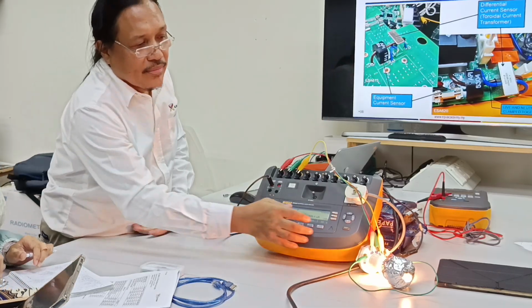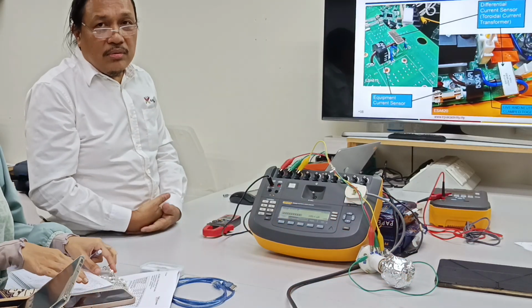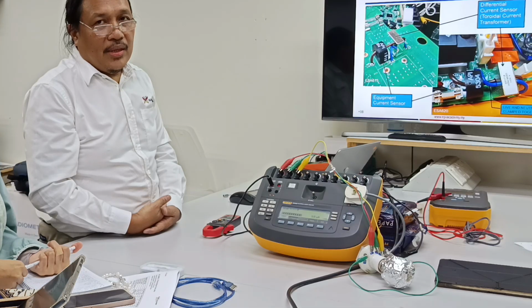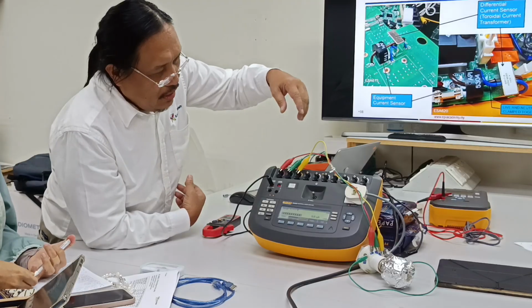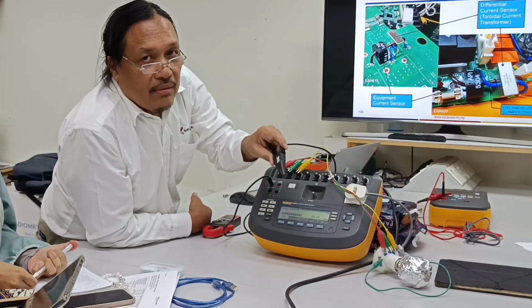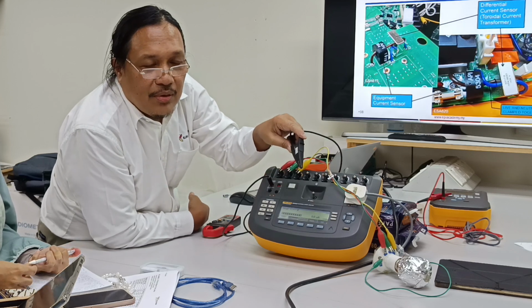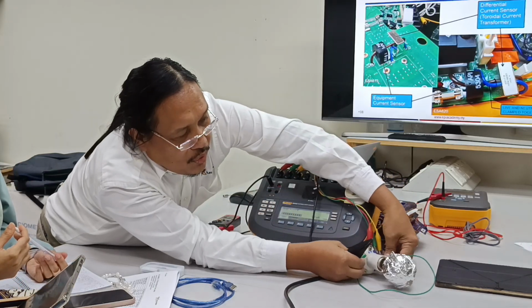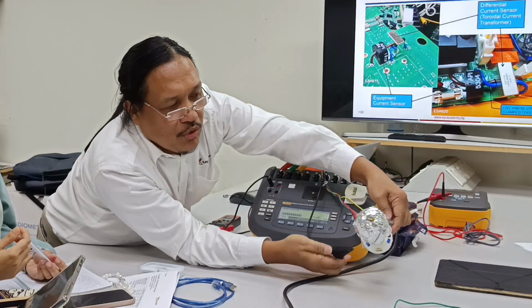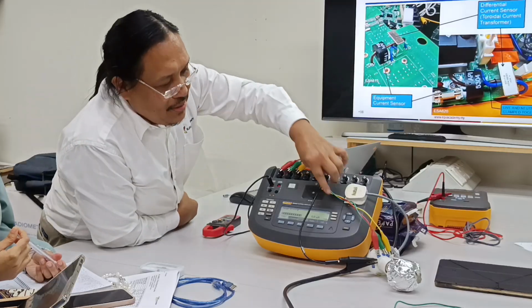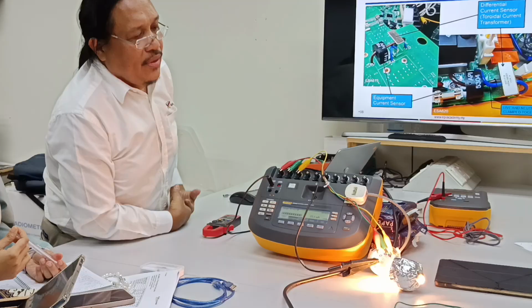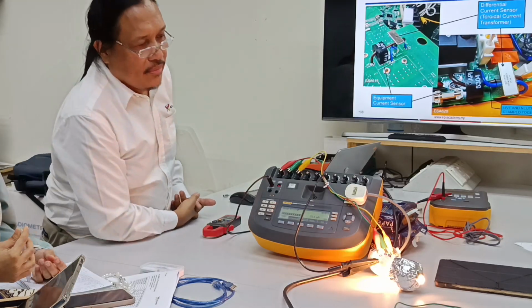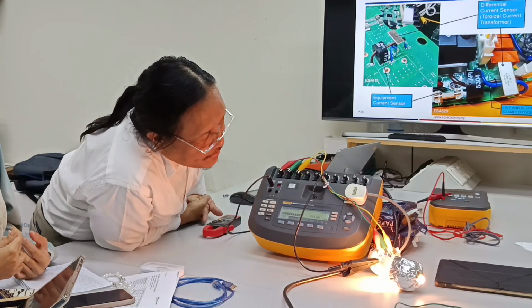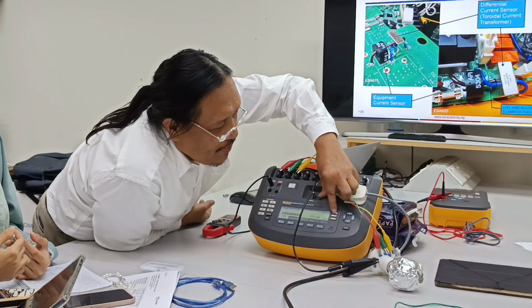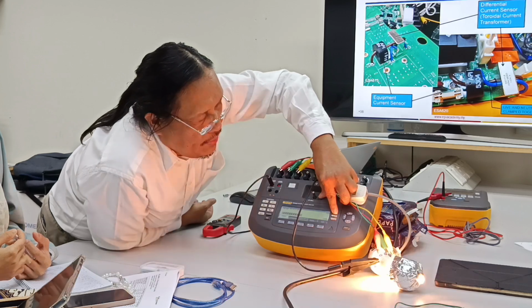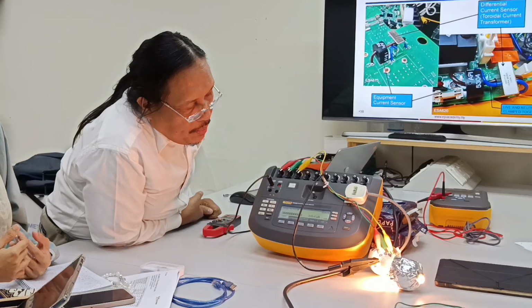I have a question. For a class 2 medical device, there's no ground. So the connection only has 2. The clip will be at the accessible conductive part or the enclosure of the class 2. So, assuming this is a class 2, from that point it will be here. There's no grounded part. Right. 22.1. Oh, it's in reverse polarity. Anyway, Class 1, 145, normal polarity.